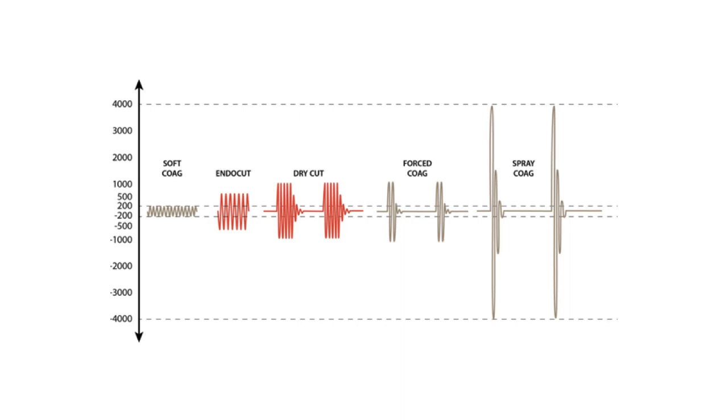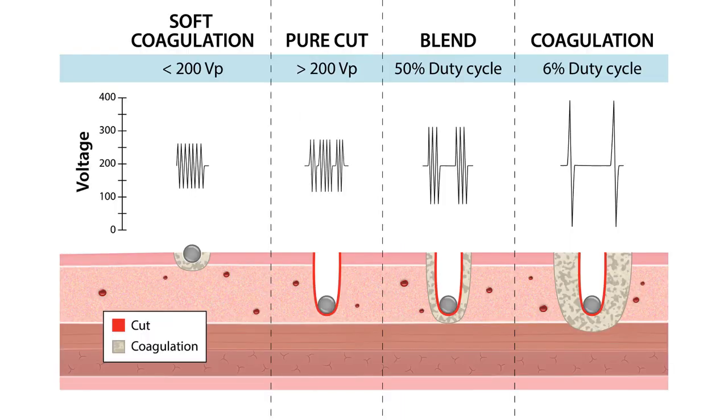Let us look at the tissue effects in relation to these voltage peaks and the waveforms. As you can see here, with soft coagulation, less than 200 volts peak, you get superficial coagulation. With pure cut, more than 200 volts peak, you get a nice clean cut.